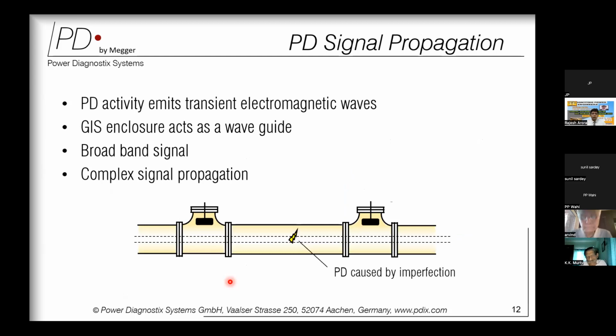Let's understand some signal propagation whenever a partial discharge occurs in the insulating medium inside the GIS. As we know, PD activity emits transient electromagnetic waves, and these waves will travel across the GIS, and the GIS enclosure will act as a waveguide which will guide this wave to different parts of the GIS, and it will cross the barrier insulator and enter the next compartment also.